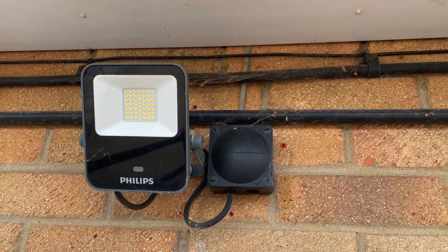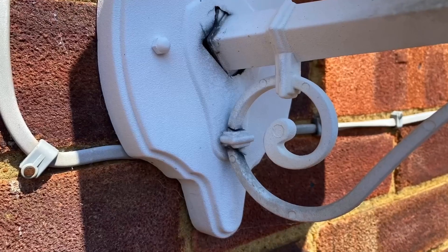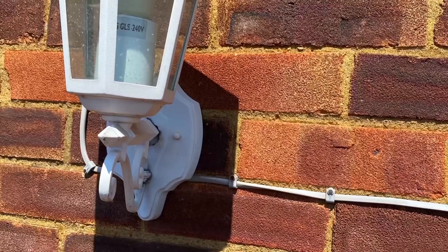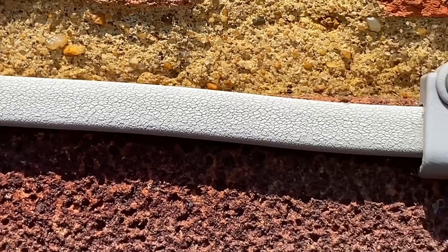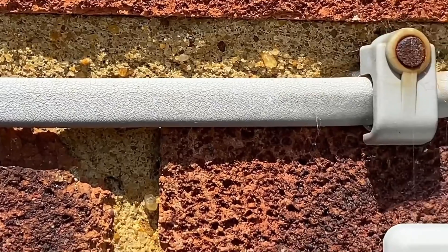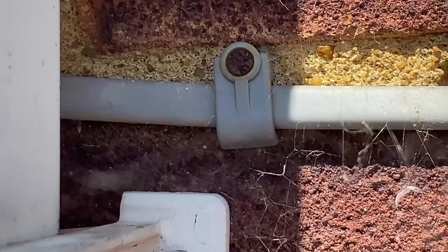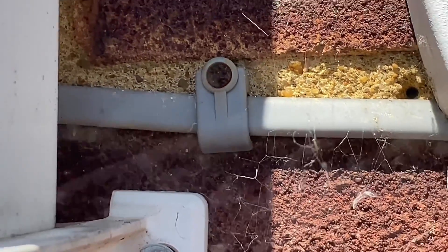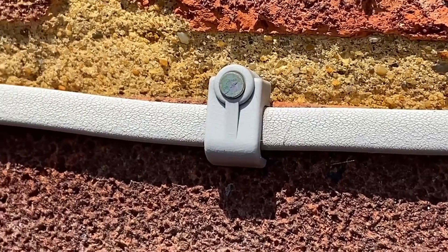We also see black conduits and black steel or armoured cable attached to the outside of buildings. So what has really happened to that grey PVC? During your study program you may hear the words UV degradation or UV radiation. What's happening is the sunlight is effectively attacking the outer PVC mechanical protection of the cable — it almost now looks like a snakeskin. If you were to start moving it, it would also be brittle, caused by that direct sunlight. But where the cable is the other side of the drain pipe, where it hasn't been in direct sunlight, it hasn't got that snakeskin or breaking down of the PVC. So when it isn't in direct sunlight it hasn't got the same degrading effect.